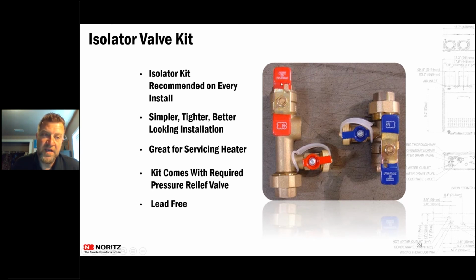But one thing these isolation valves are for is that tankless water heaters do require maintenance. We do require, if you do not have filtration in there, that these units are flushed once per year. So these little valves that are sticking off the side of this, that's what these are for, so you can isolate just the unit within itself. And then you can flush those units with either a CLR type mixture or a food grade vinegar, which we'll cover here in just a little bit. But the isolation valves also have your shut-offs for the hot and the cold already built into them as well. So we highly recommend that isolation valves are installed on every single unit that you are installing. So any questions on the isolation valves?